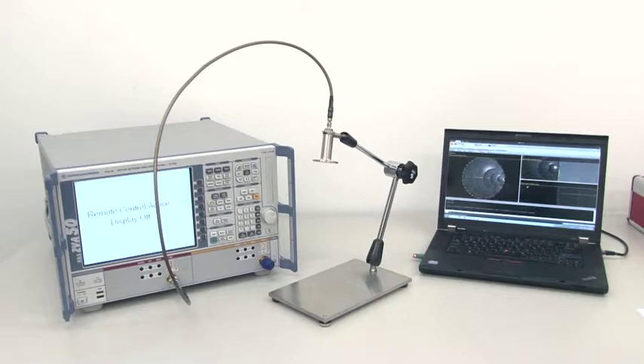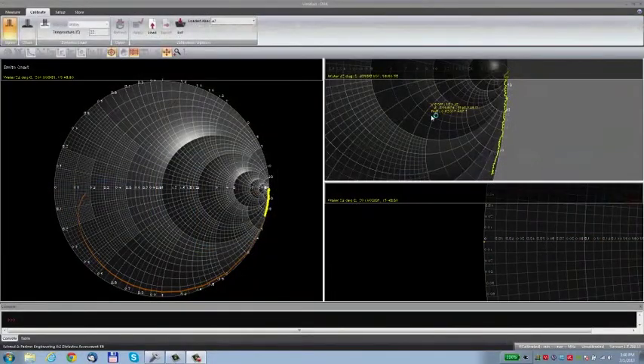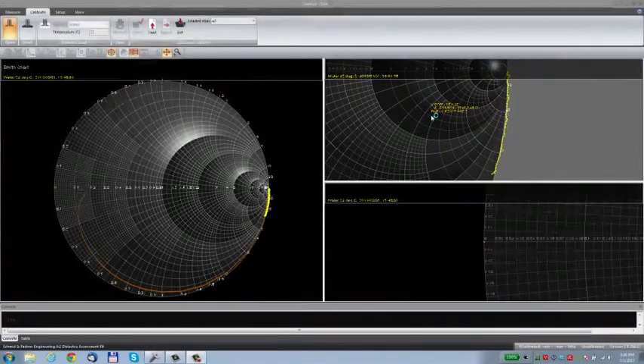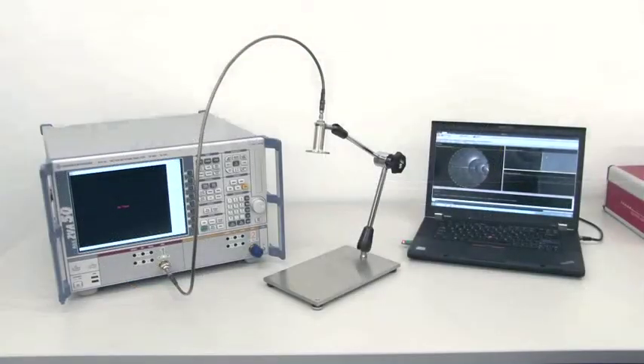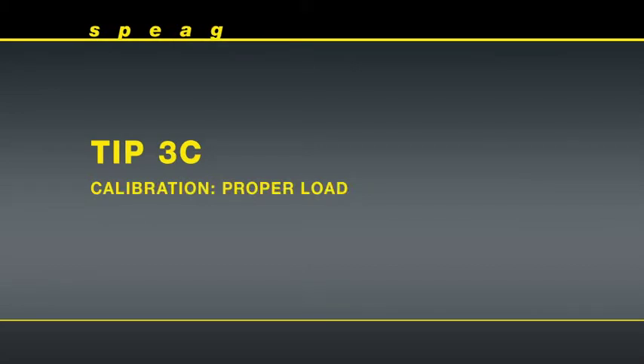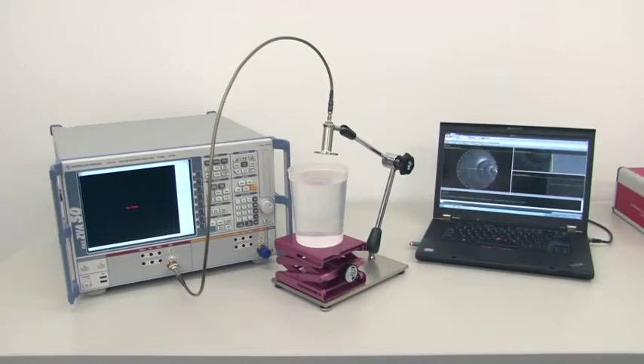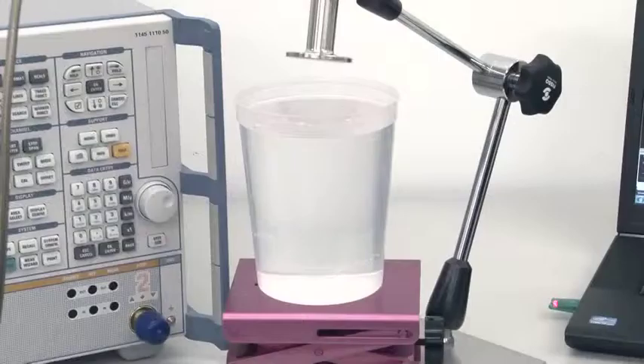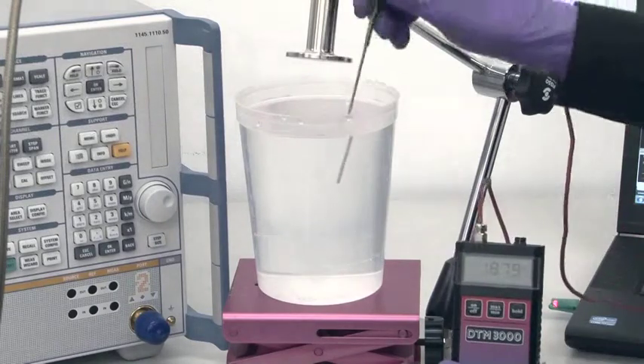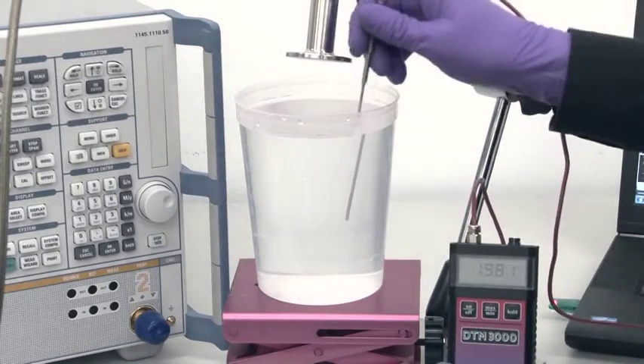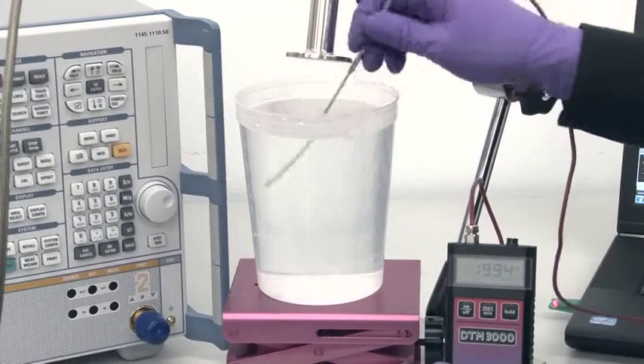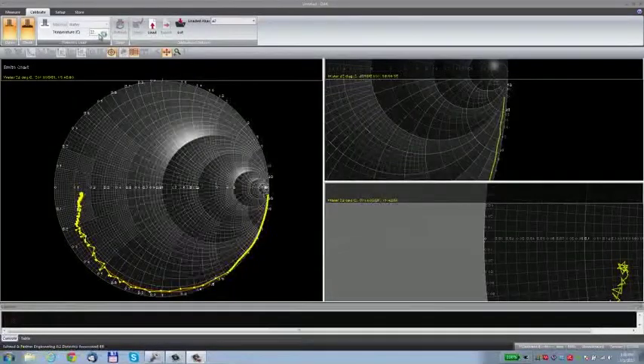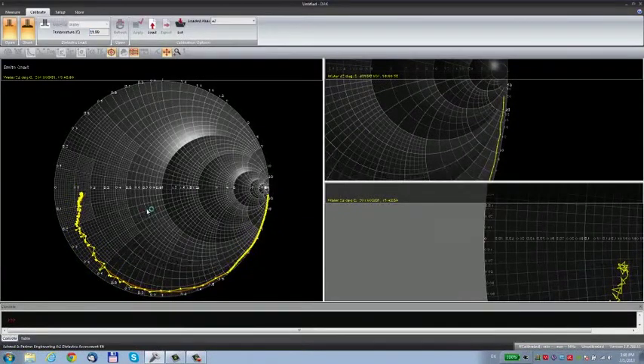The open calibration standard is the air. If you see any movement of the curve during the calibration, for instance by the open validation, it indicates that the cable is not stable mechanically. For the load, we use well-characterized polar liquids, such as water, methanol, or ethanol. Measure the precise temperature of the liquid. By stirring it, the temperature can be homogenized. Type the temperature in the software.